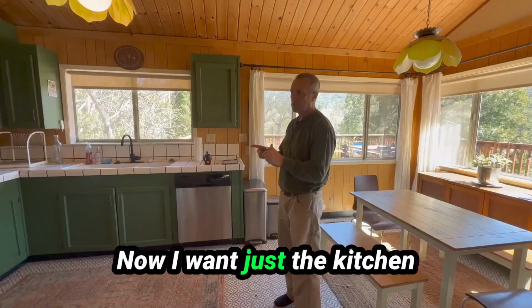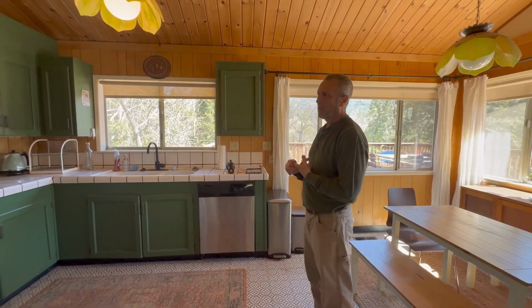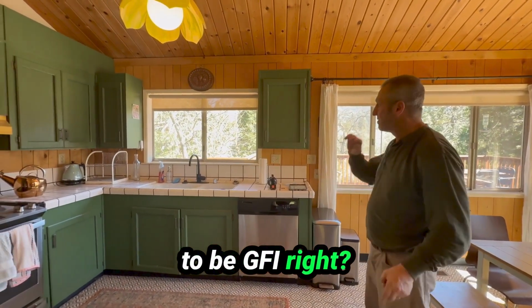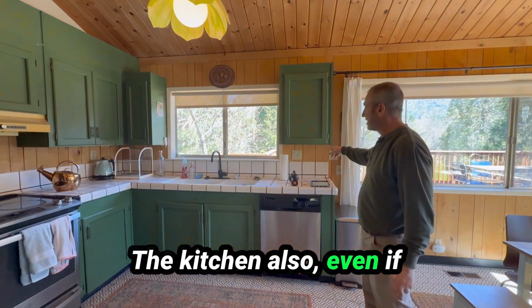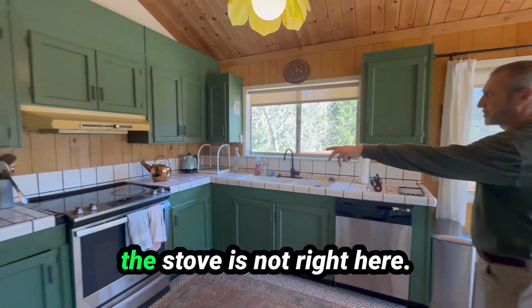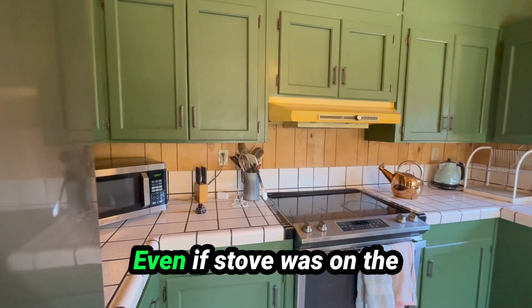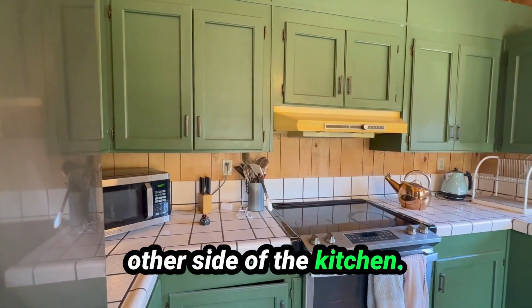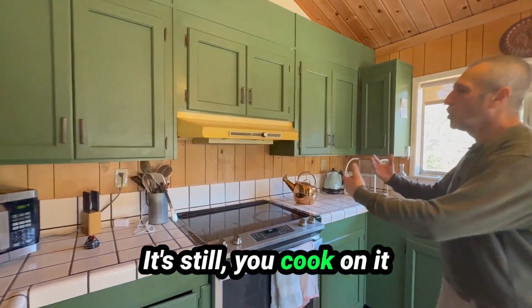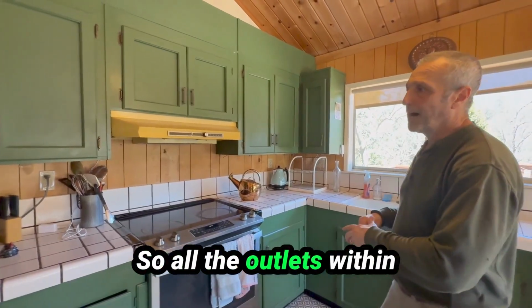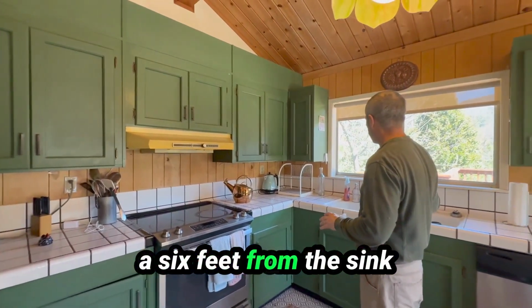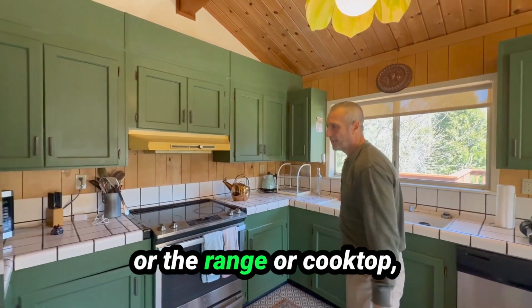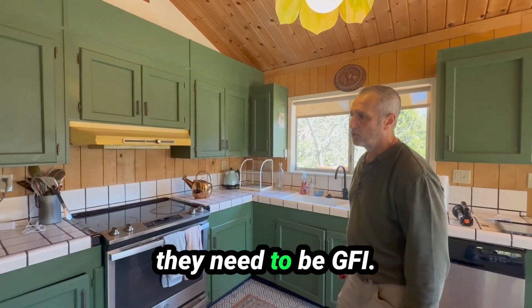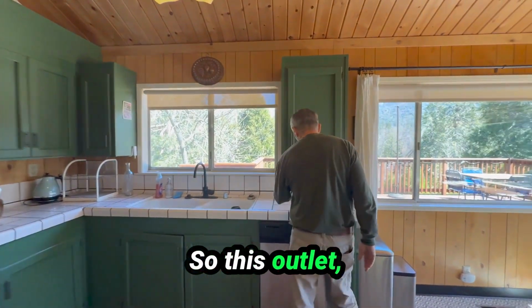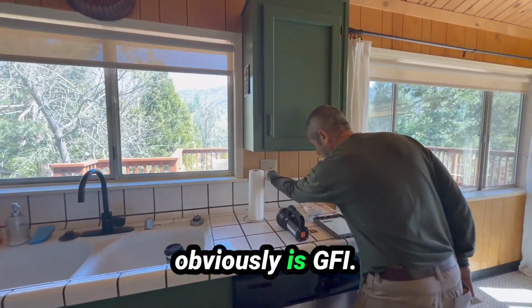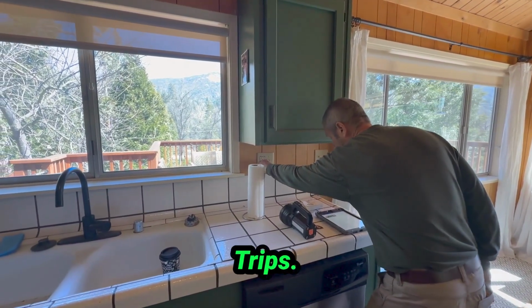Okay, now I want to check the kitchen area and the bathrooms. The bathrooms have to be GFI, right? The kitchen too - even if the stove is not right here, even if the stove was on the other side of the kitchen, you still cook on it and water is present. So all the outlets within 6 feet from the sink or the range or cooktop need to be GFI. So this outlet obviously is GFI, trips.